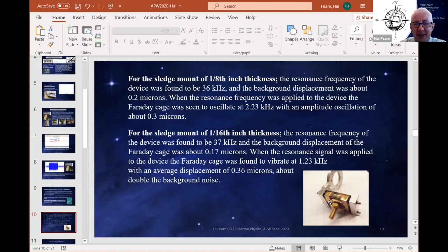So with the sledge mount, again, I used two different thicknesses of bracket for this L bracket on the top here. For the 1/8 of an inch, I found that the resonant frequency was about 36 kilohertz, and the background displacement about 0.2 microns. When the resonant frequency was applied, the Faraday cage was seen to oscillate at about 2 kilohertz with this sledge, and the amplitude of the oscillation went down to 0.3. So that's half of the displacement that you were seeing with the regular L bracket. So this sledge does in fact reduce the amount of oscillation that is transmitted to the Faraday cage.